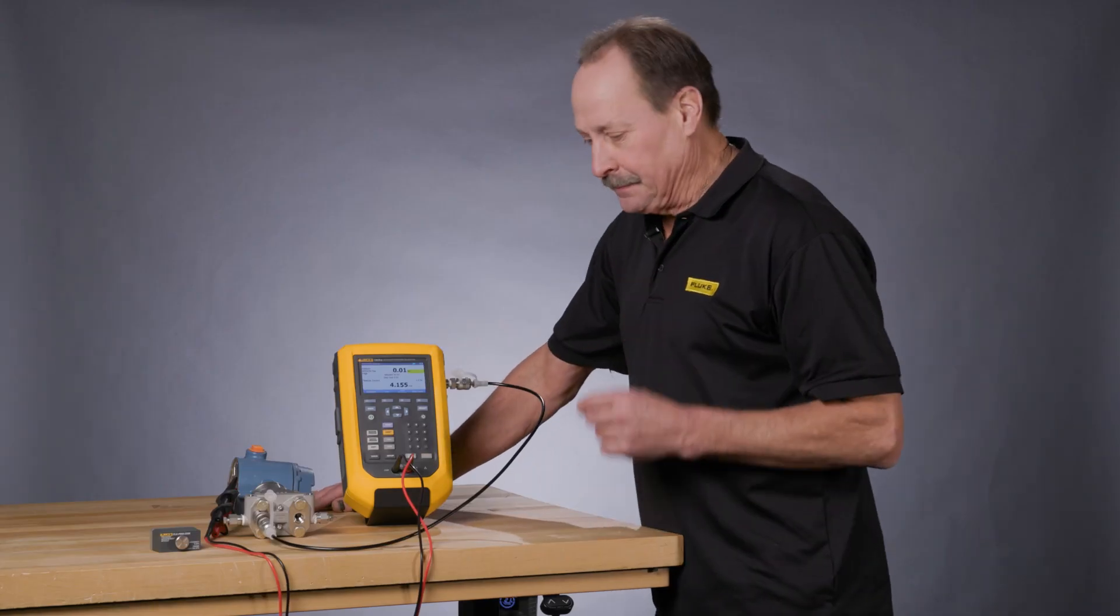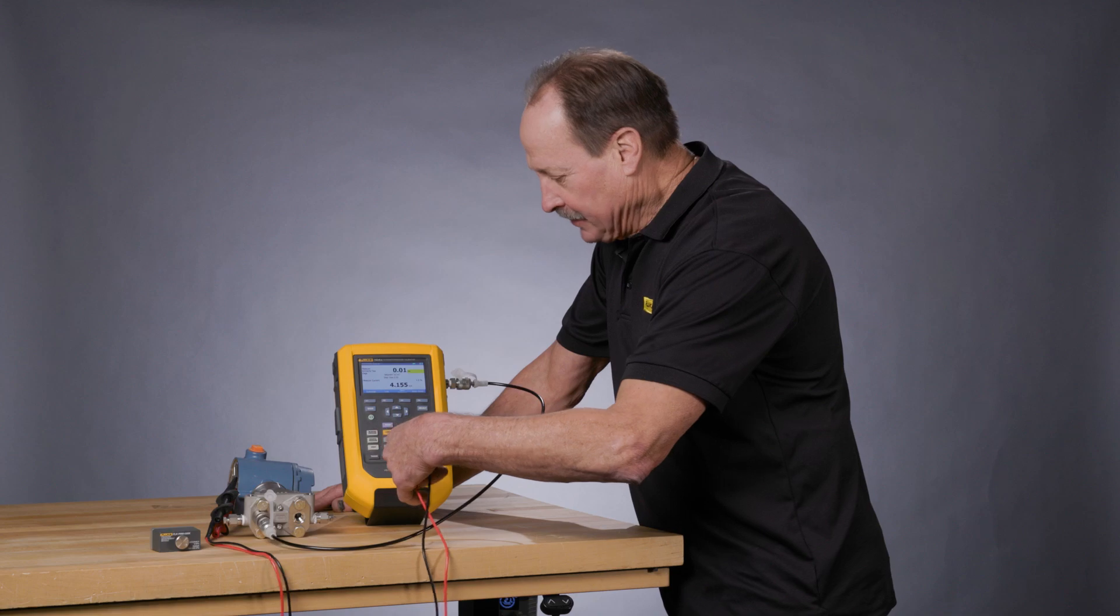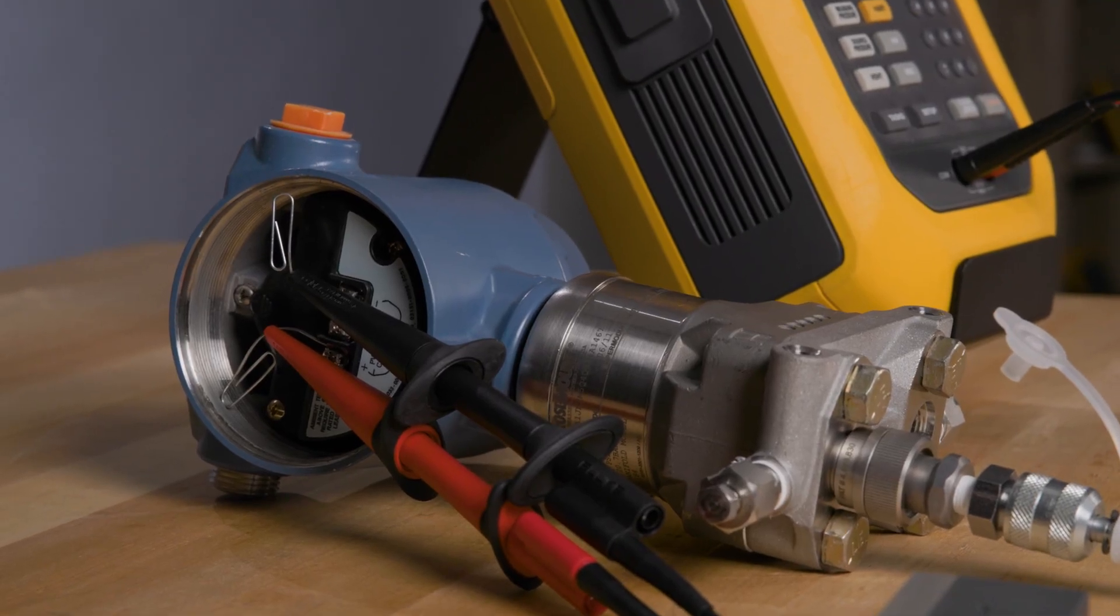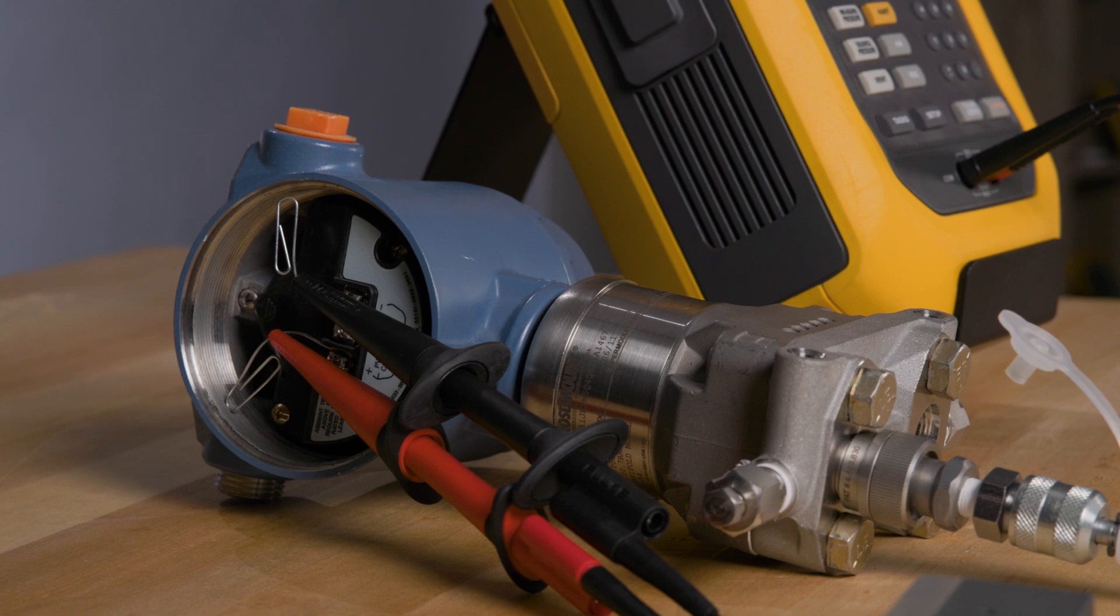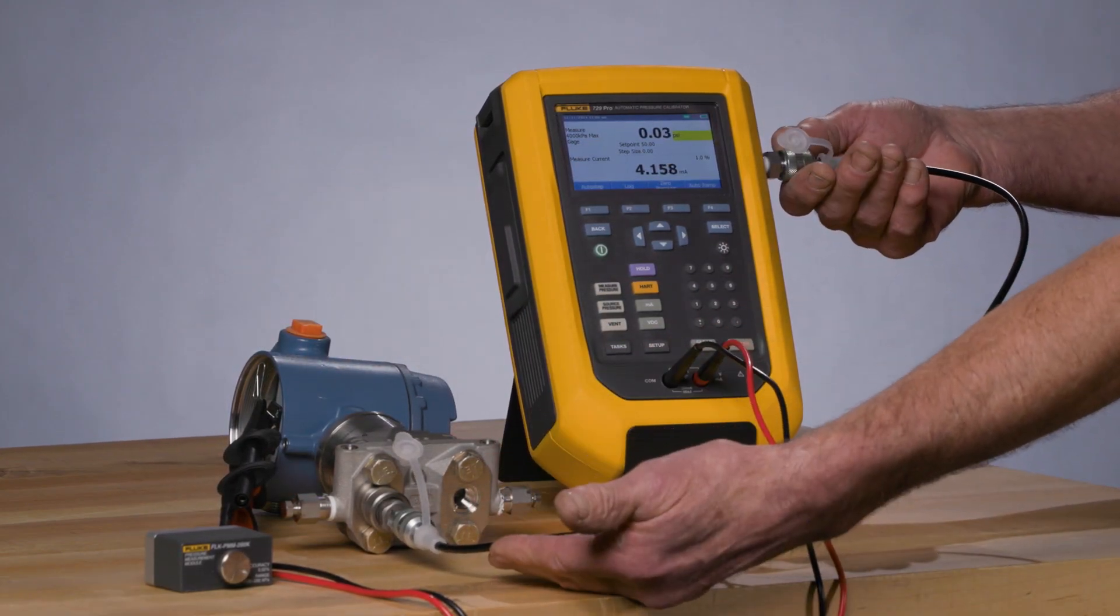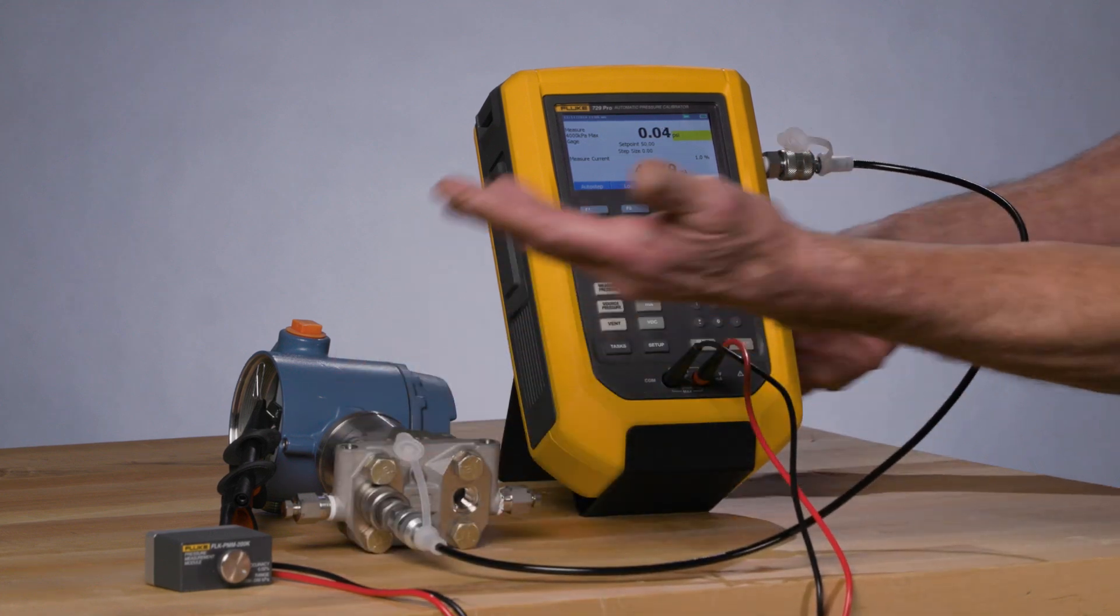To begin the test, we have to get all connected to the milliamp jacks, and we'll be powering the transmitter and recording the milliamp signal as drawn from the 24 volt supply, and the output pressure of the 729 Pro is connected to the input of the transmitter.